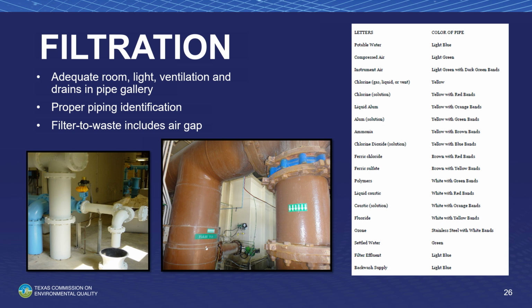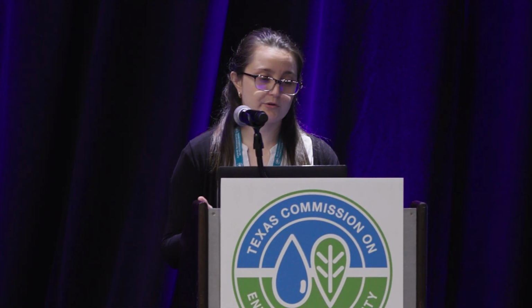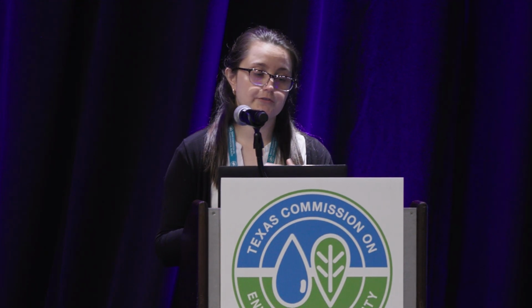includes an air gap. So over on the side, I have a list of general color coordination that you can use for your piping throughout your plant. This also includes chemical piping. So in lieu of labeling what is there, so instead of saying raw water on a pipe, if you use it with this brown color, I can understand that this is a raw water pipe. Settled water tends to be a green color, and then anything filtered is going to be a blue color. Same thing with chemicals, different patterns of colors will indicate to me what chemical is being transferred through that line.